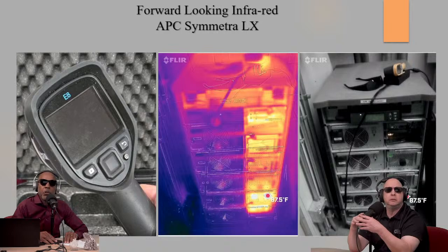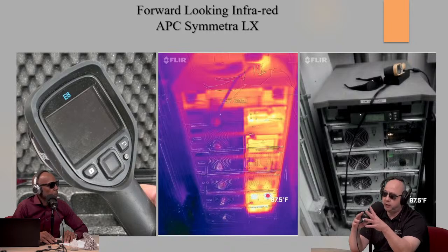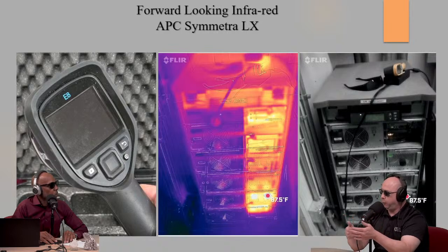Next question from Justin: do you ever overload the UPS on purpose to see if the unit will go to static bypass? Depends on the configuration. If it's like a 20 or 30K, I won't do it, because some of these modules are older ones we're refurbishing, so we do want to tax them, but we also don't want to blow something up and lose inventory, having to start over from square one with another piece.